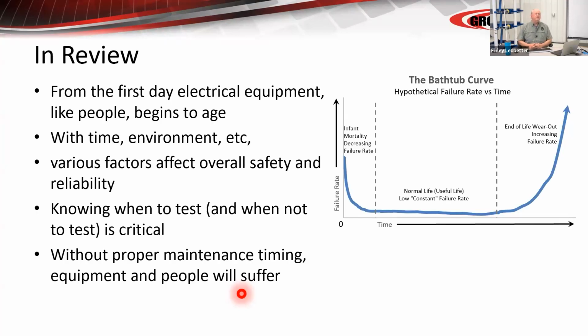If we're going to go back and review what we've talked about in the first 2 segments, what we're doing here is, the day that you get your equipment, actually the day it's built, the day it's specified, it starts to age. And it ages as far as obsolescence goes. It ages as far as operating conditions go. It ages as far as where it is in its life cycle. Time, the environment, if it's repetitive duty application, a lot of equipment's not designed for repetitive duty, yet it gets put into those applications and causes a lot of problems.